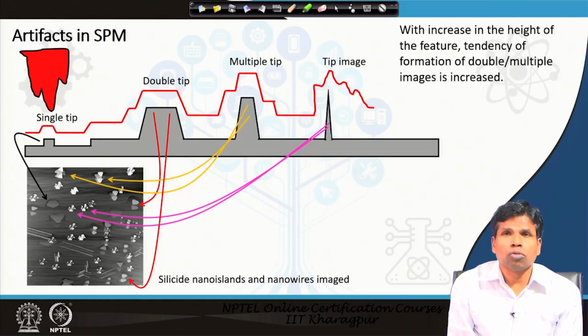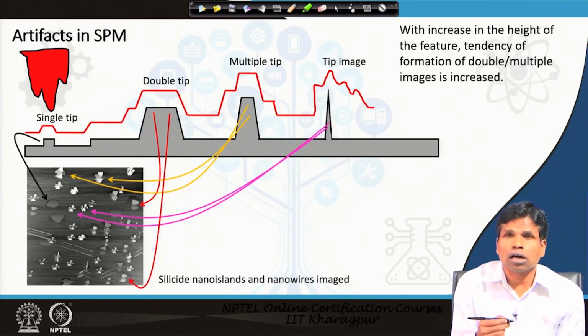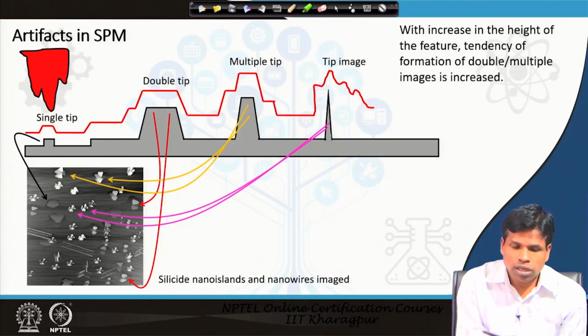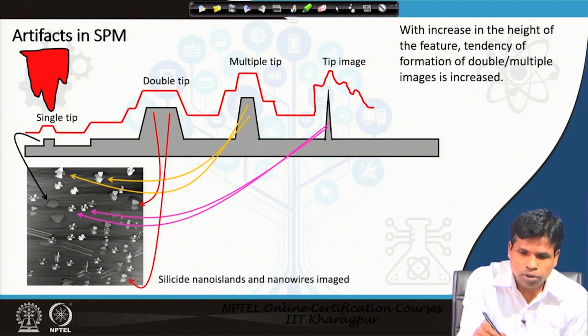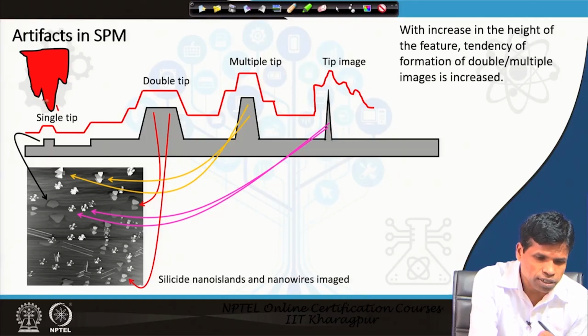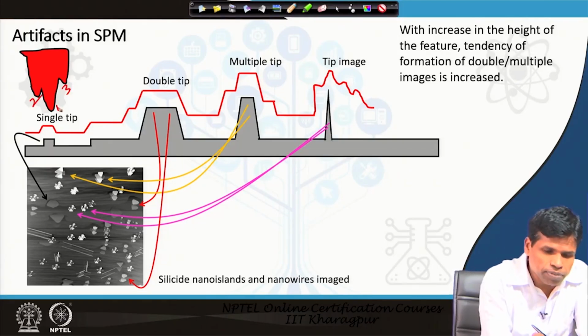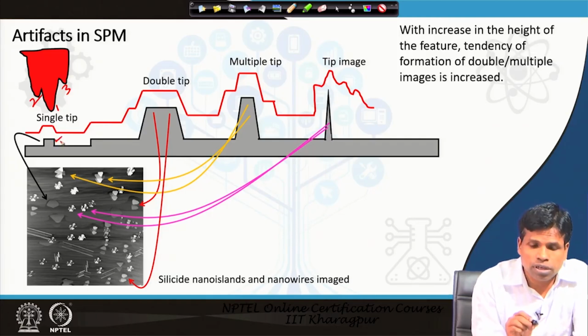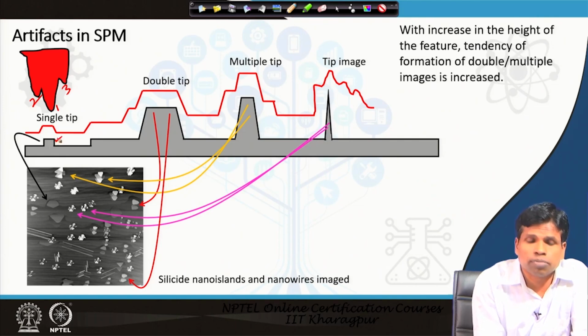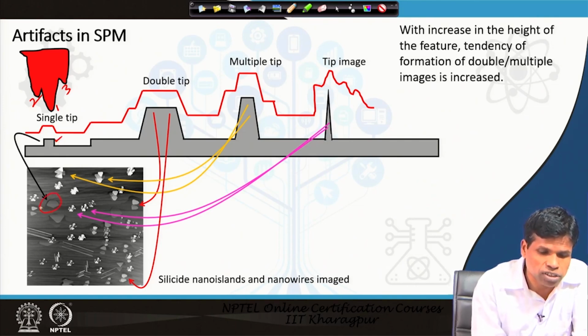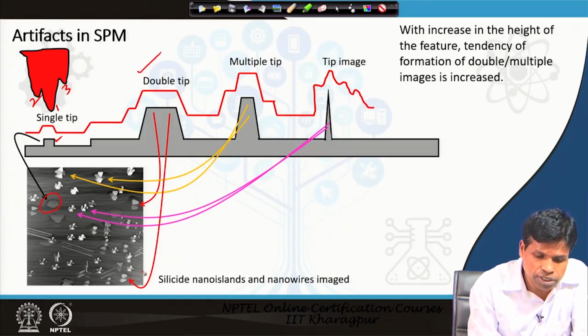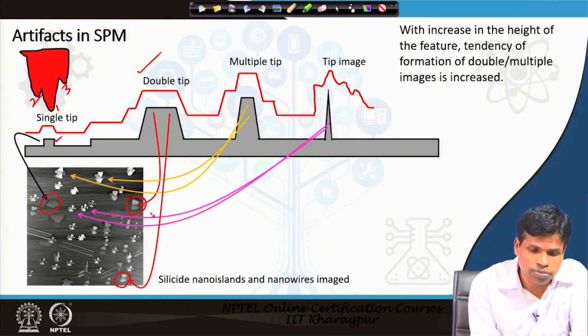Artifacts can also be due to multiple tips. If multiple tips are there, then they will show different types of information in the image that you see here. For example, this is a multiple tip: tip number 1, tip number 2, tip number 3. If the height of a single feature is not very tall, then we could see the feature like this. But as the feature height increases in the sample, at those places we see double tip information. As you see here, the same feature looks like 2 repeating features. This is due to the double tip.